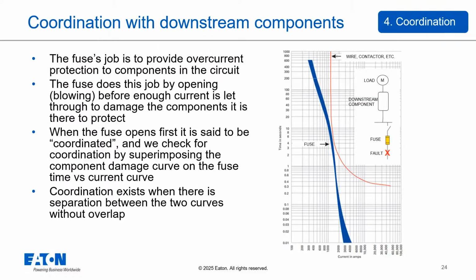We verify coordination by looking at the time current curve again. We superimpose the fuse's time current curve with the damage curve of the downstream component. Coordination exists if the fuse curve is always below and to the left of the component damage curve, meaning that the fuse operates faster at any given current level than it takes to damage the component. There needs to be clear separation between the two curves.